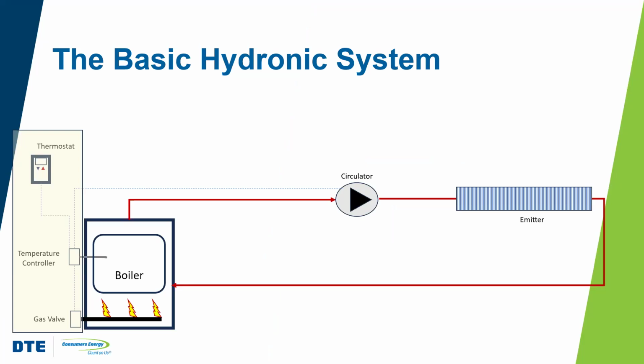So to that basic system, right, we add a couple of controls, right? One of the first things we add is a centrally located thermostat. This is going to be somewhere within the house, and this is going to tell the boiler when to turn on, right, based on its set point, based on that space set point.